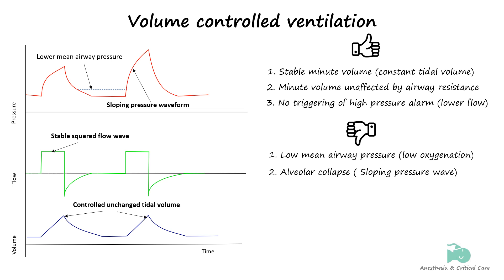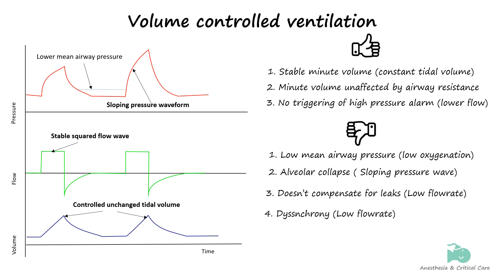In cases where there is a leak, mean airway pressure can become unstable. The constant flow used in volume-controlled ventilation might not adequately compensate for intermittent leaks. If the rate of the leak matches the inspiratory flow rate, no volume will be delivered to the patient. Lastly, insufficient flow during volume-controlled ventilation can lead to patient-ventilator dyssynchrony. If the patient's respiratory demand increases during a breath and the ventilator cannot provide the necessary flow, it may fail to meet the patient's needs.